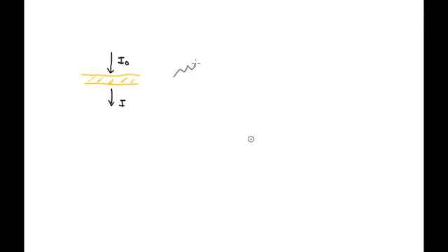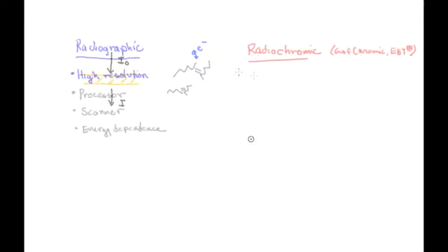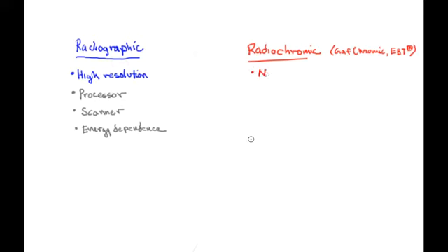They're diacetylene molecules, and they're embedded in a thin plastic, typically a few tens of microns thick, that sits on a substrate. And then you have a reaction that happens when radiation comes in. If you have a charge or an electron, there's a cross-linking of these monomers. And the result of that cross-linking is that it becomes optically opaque. So the film darkens.